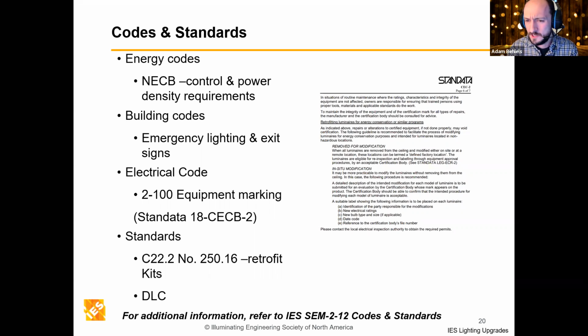Just a couple standards to note: C22.2 number 250.16, it's more of a manufacturer standard for retrofit kits. And as far as a quality standard, DLC - not every vendor subscribes to it, doesn't mean they're bad quality, but it can be helpful if a client throws a luminaire at you that a salesman told them about and you haven't heard of before. Maybe look at their DLC listing and see where that sits. Keep in mind there's a lot of gray label listings in there that get rebranded by vendors, which can be confusing at times, so you'll have to follow up with the vendor to get their gray label unit number to check it there.